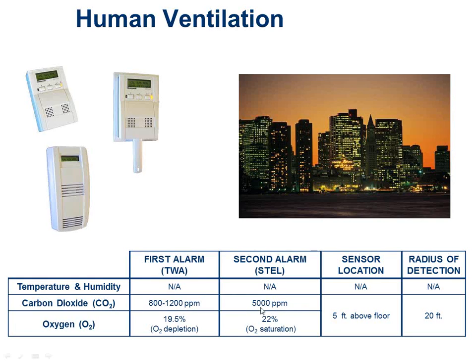I am showing a limit up here of 5,000 parts per million. That's not because something bad is going to happen and you're going to die. It's just that if I get to higher numbers up there, that probably means either there's something wrong with my sensor or I have some sort of problem that I need to deal with from the BAS standpoint, so I do want to alarm you.